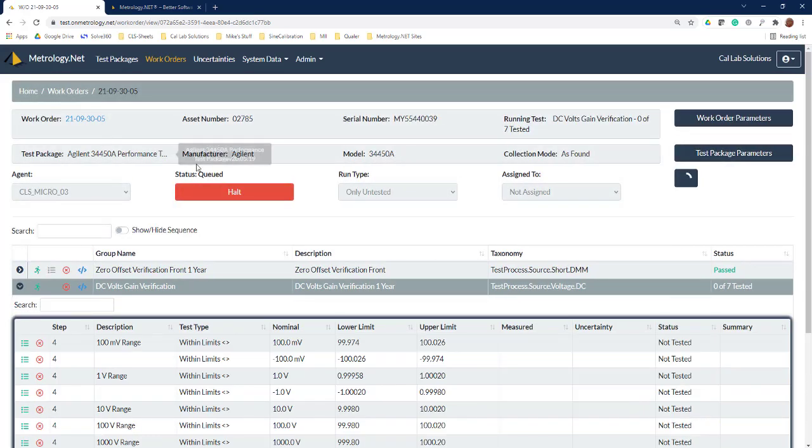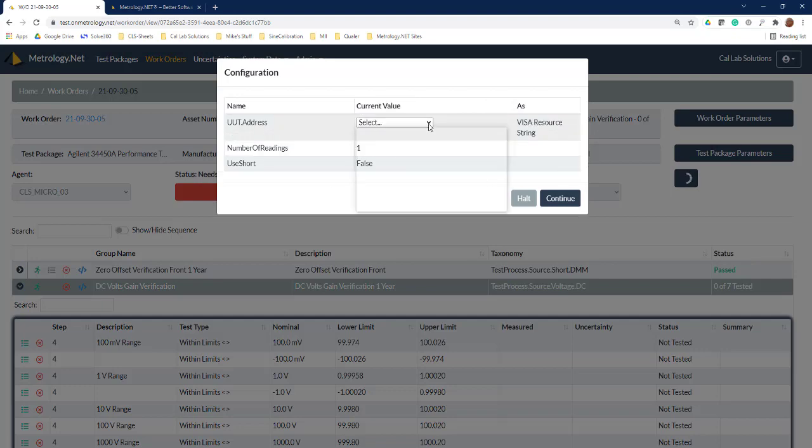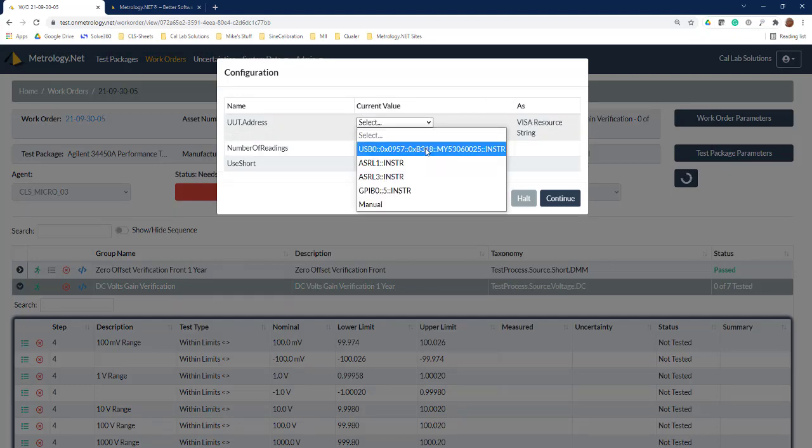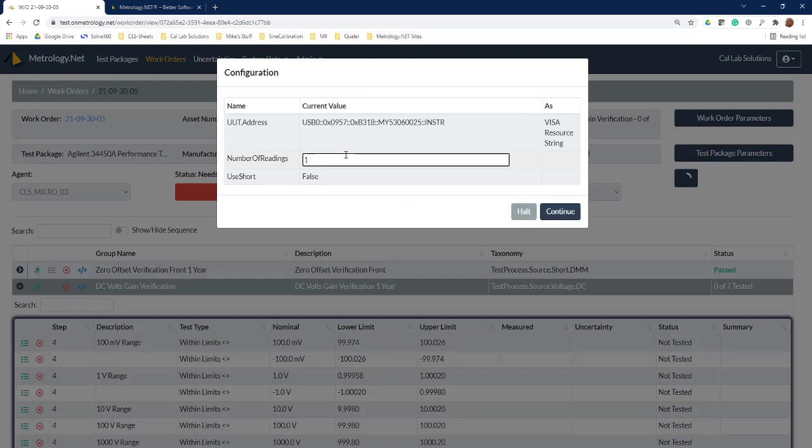Now you can see that we've queued that work. The workstation is now going to download those data points and start the calibration for us. It comes up and says the UUT is not set, so we'll select our unit under test.